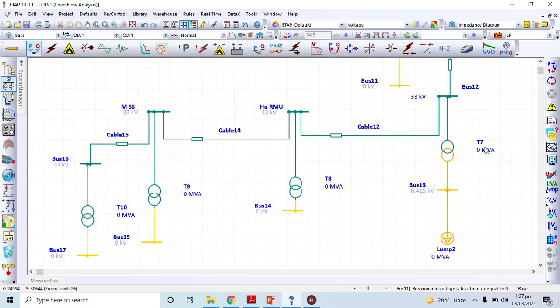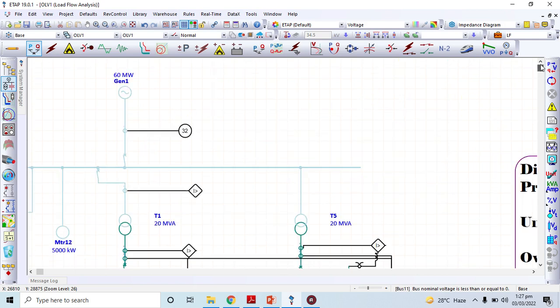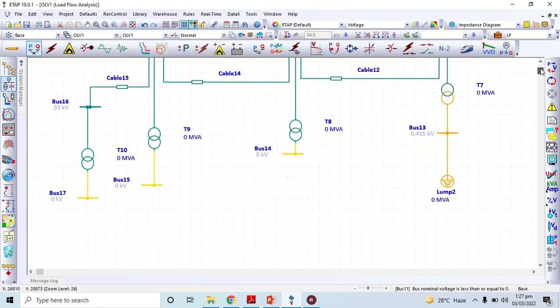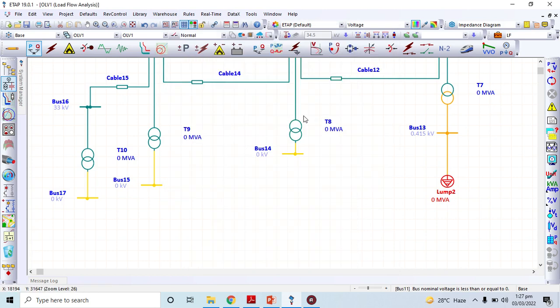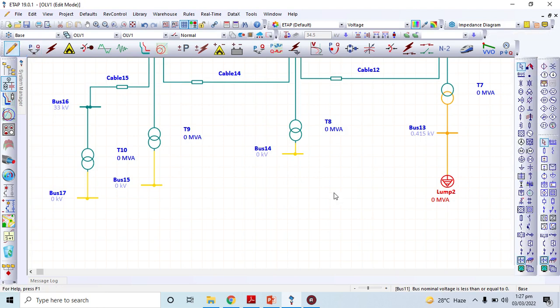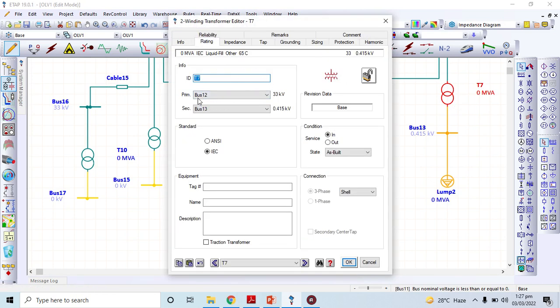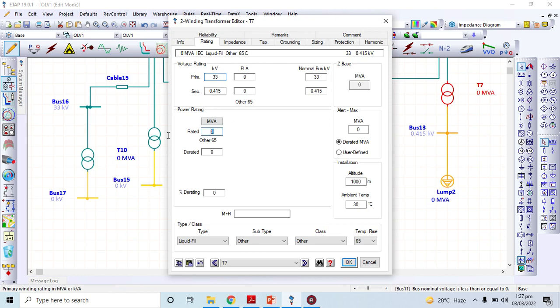Our task is to size the transformer. We have a network which I converted into a voltage diagram with different color coding. I connected a load of 100 ampere here, and I will connect some other loads to other transformers. The rating I didn't give yet — I just give the rating of the existing transformer. By sizing a transformer, you are observing how much extra you can utilize it and what the safe limits are. This transformer rating is 2.5 MVA.